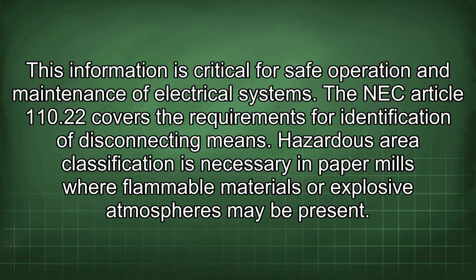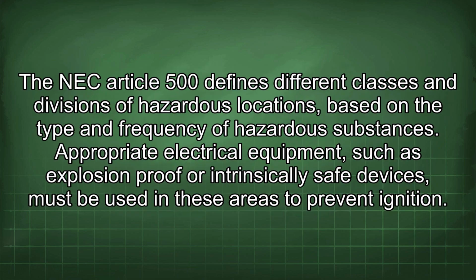Hazardous area classification is necessary in paper mills where flammable materials or explosive atmospheres may be present. The NEC Article 500 defines different classes and divisions of hazardous locations based on the type and frequency of hazardous substances. Appropriate electrical equipment, such as explosion-proof or intrinsically safe devices, must be used in these areas to prevent ignition.